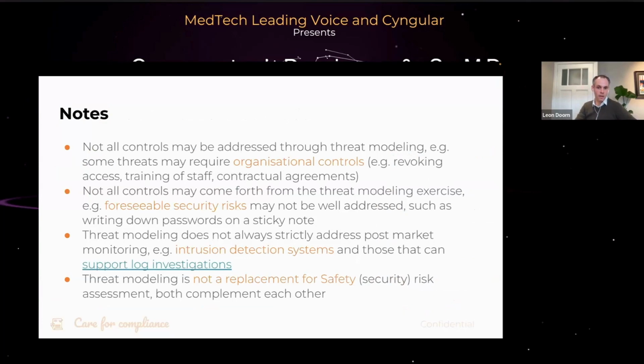One of the other controls that also do not necessarily come from the risk management, threat modeling exercise are foreseeable security risks. So, for example, writing down passwords on a sticky note, just a very simple example. I don't think that's properly addressed through the threat modeling. It could be, but it might not always be. Another one to consider is that threat modeling does not always strictly address post-market monitoring, for example, intrusion detection systems. When you write those down as a control, again, I think that's more of an organizational control. So it might fit a little bit under the same note that I have here.